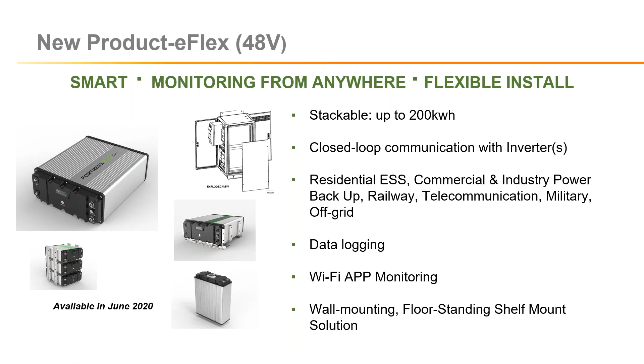Regarding lithium batteries, one key thing that makes them different from a lead acid or typical gel battery is the battery management system. For example, in the eVault 18.5 and the eFlex, we use a contactor-based BMS. Like a MOSFET-based BMS, it protects against overcharging, deep discharging, overheating, overcurrent, short circuit, and open circuit, safeguarding the cells.